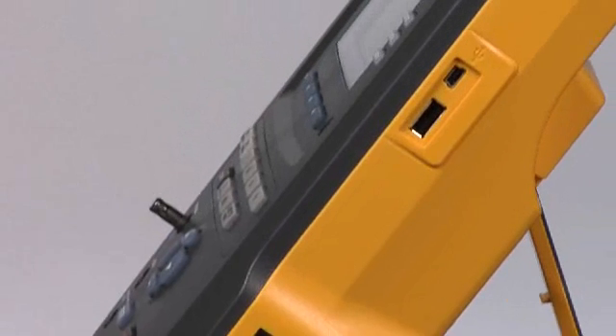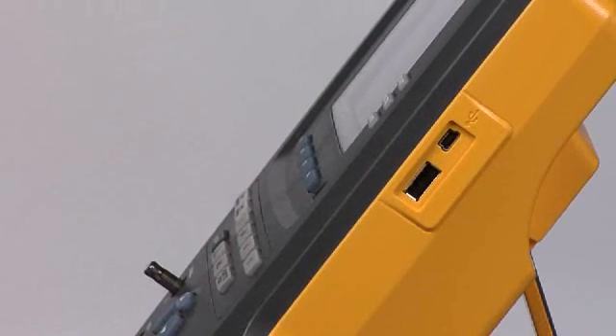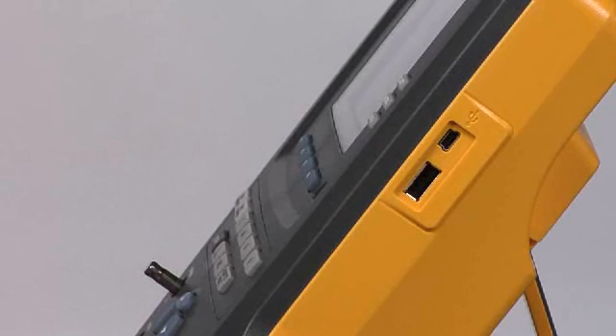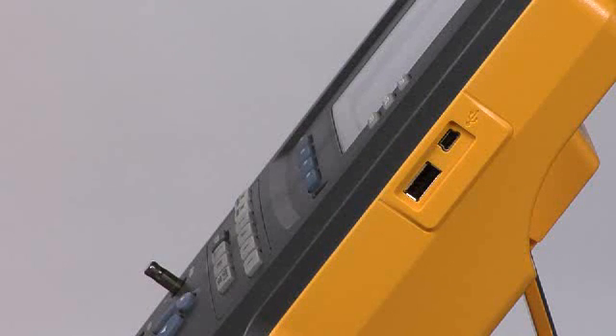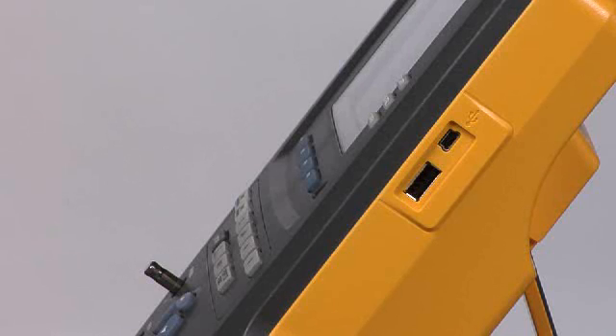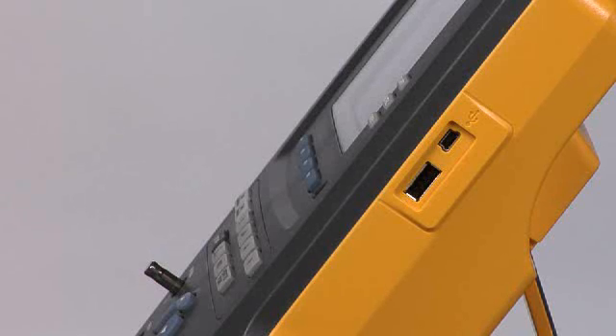Moving up higher on this side of the device, we see the USB ports, and there are two of them. The mini USB port is for connecting the ESA615 to your computer, for instance running the Ansur test automation software or the Ansur Mini plug-in for the ESA615. The larger of the two USB ports is for connecting keyboards, barcode scanners, and the like.